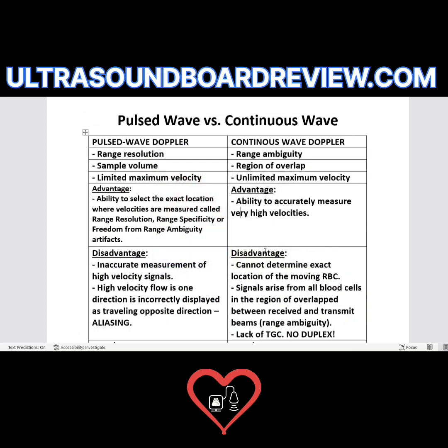Continuous wave Doppler doesn't have that advantage. When you run continuous wave Doppler, you're getting velocities all the way up and down that sector. Range resolution is the first advantage that pulse wave Doppler has over continuous wave Doppler.